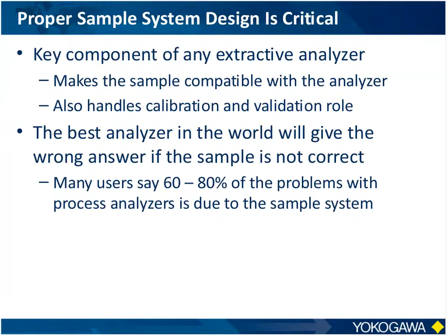So it's critical that the sample systems are designed properly, because it doesn't matter if you have the best analyzer in the world. If you've introduced a bad sample to it, you're going to get a bad answer. So most analyzer packages require at least some type of engineering review of the sample conditioning system design. Even if it's a standard application, you need to make sure that that application fits that standard design.